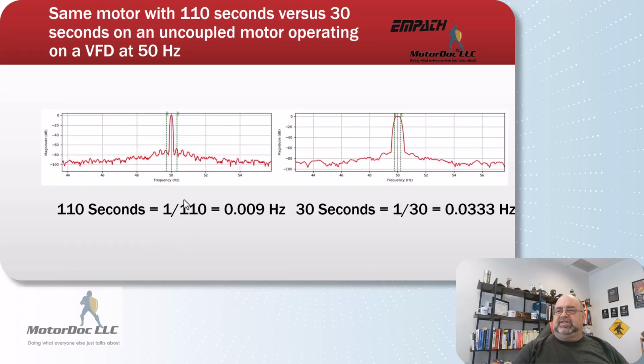Here's a good example. This is a motor with a rotor bar issue, a casting void, so not something that'll be condemned, even though the value is a little on the high side. But they've got a lot of them because I've got harmonics of it. I'm running the motor in this case by itself, so I'm seeing those. But if I took just a 30-second data set, those pole pass frequencies, these are identical, it's the exact same set of data, we just chopped it down to 30 seconds. You can see the pole pass frequency hides in here. This would be my rotor bar related stuff.